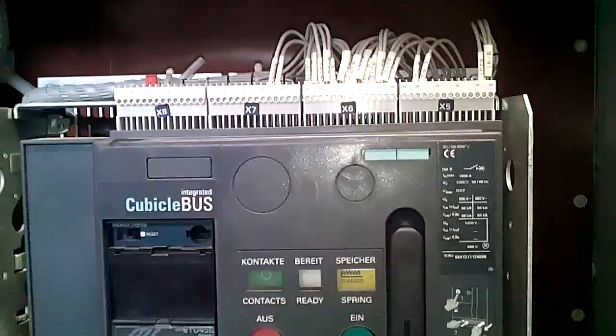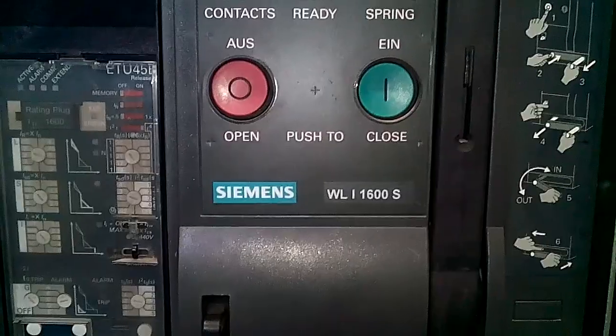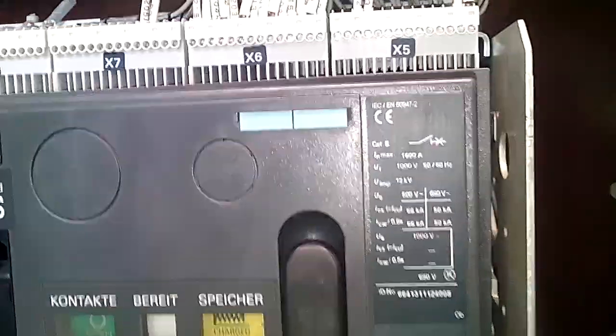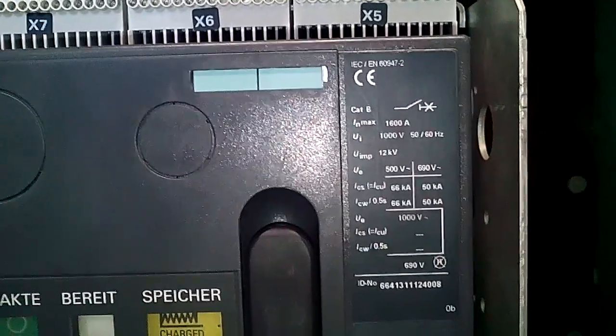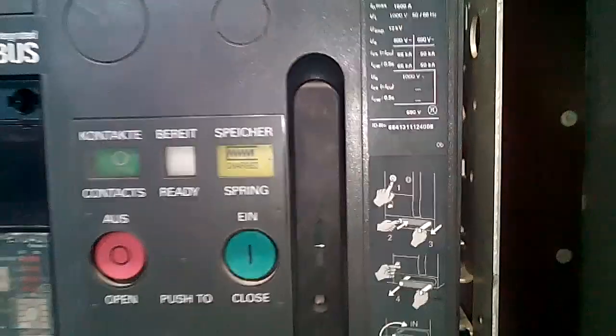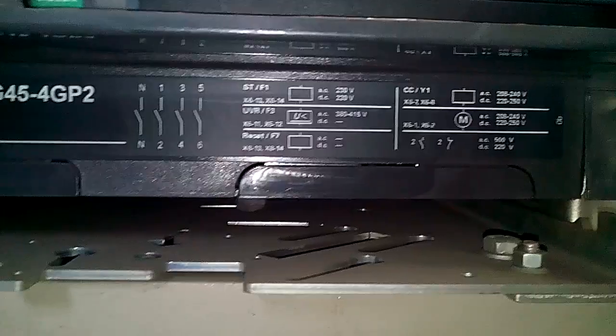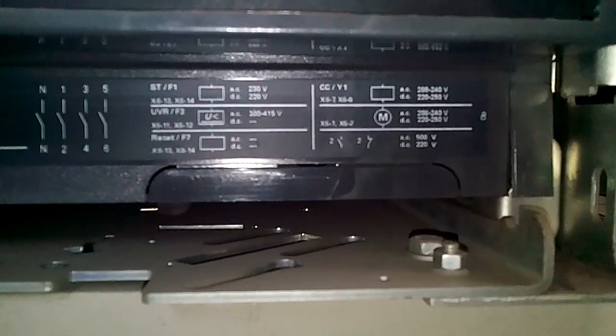Hello guys, today I am going to show you a Siemens ACB. The model number is WL 1600S. As you can see, IMAX is 1600A. This is a 4-pole breaker — R, O, I, B and neutral — so I have 3 shunt coils.